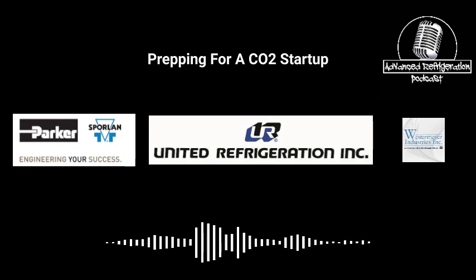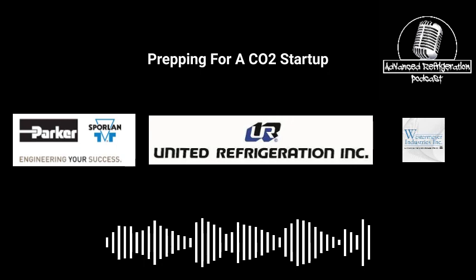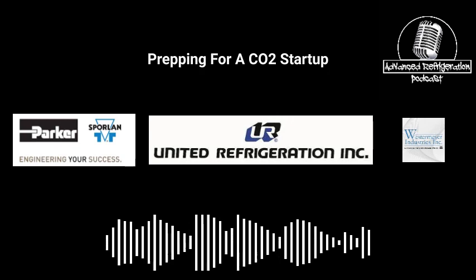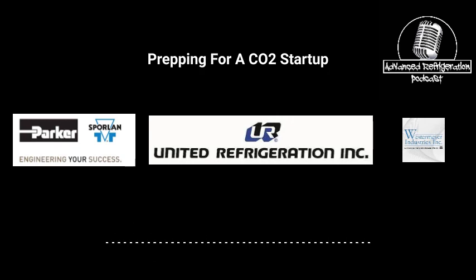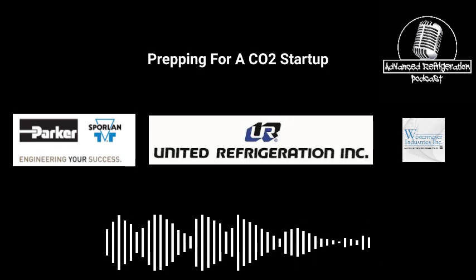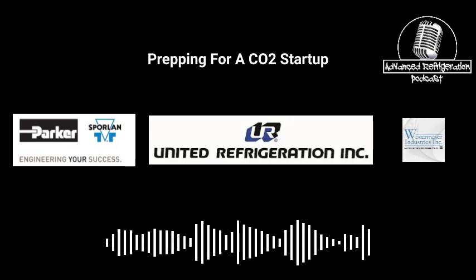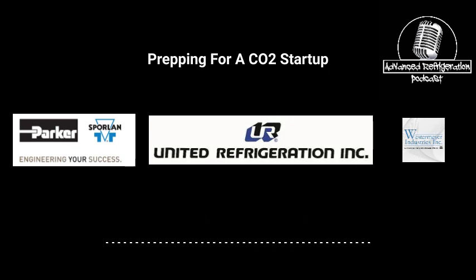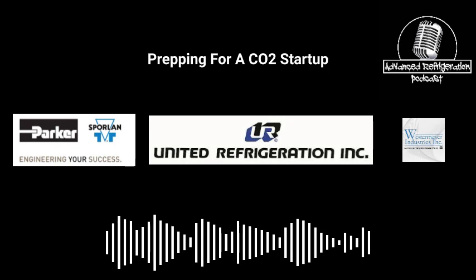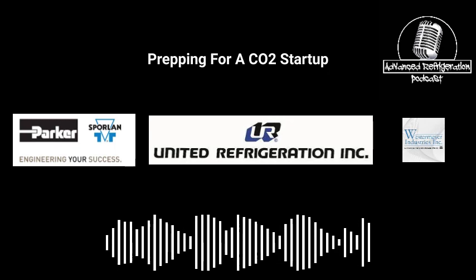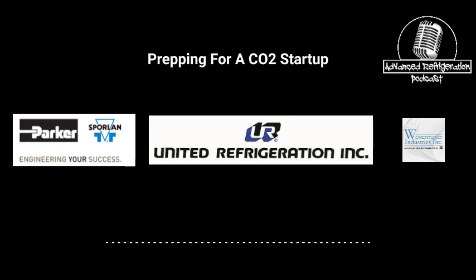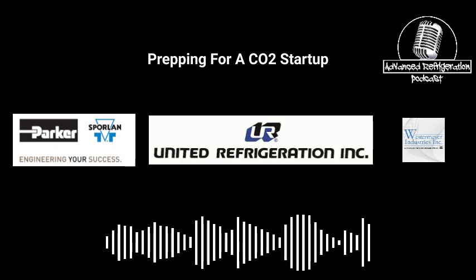I'm going to be honest, the last like 5 racks I've done, we're not using iCads anymore, because technically those are done. Yeah, what are you using for the HPV? They're just using Danfoss ICMT valves. Big silver guys with the pressure transducer already on it? Yeah, or a Sporlan. This rack I'm doing right now has a Sporlan valve on it.